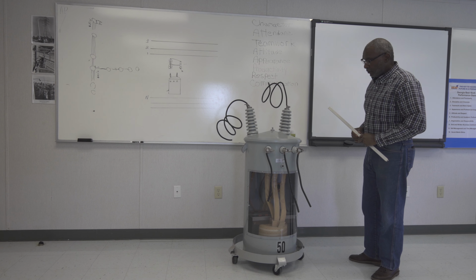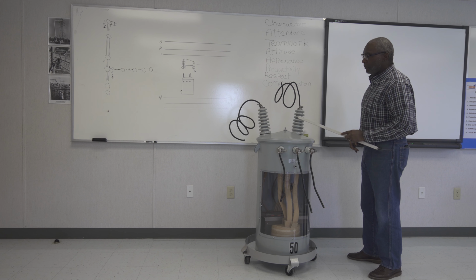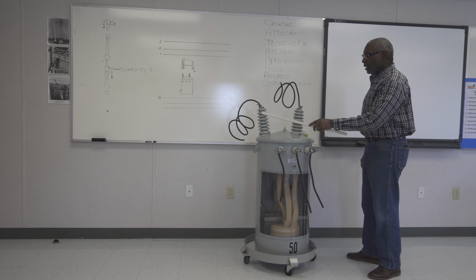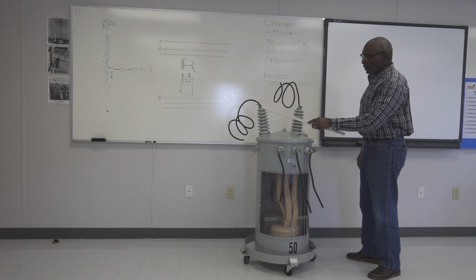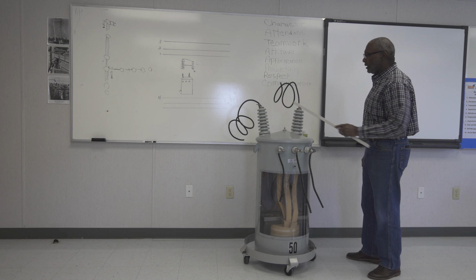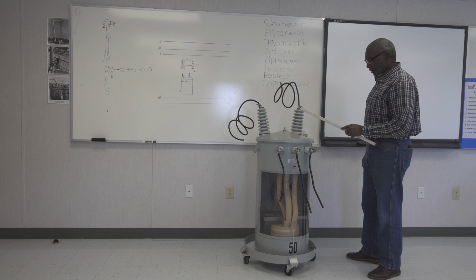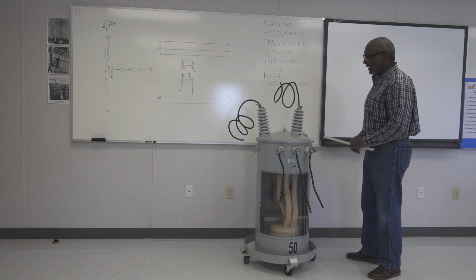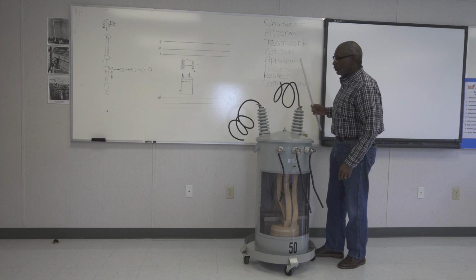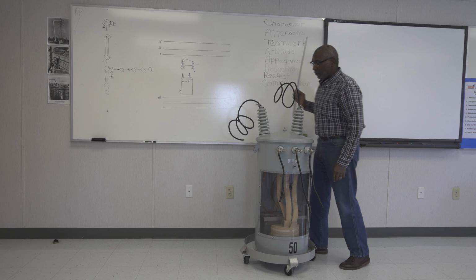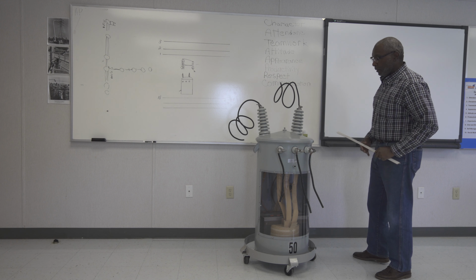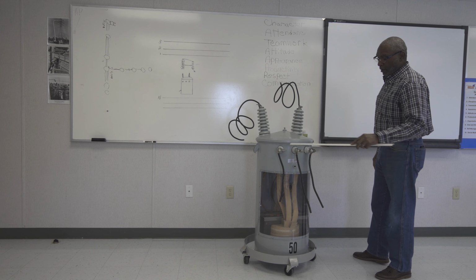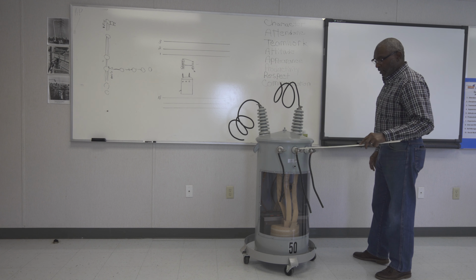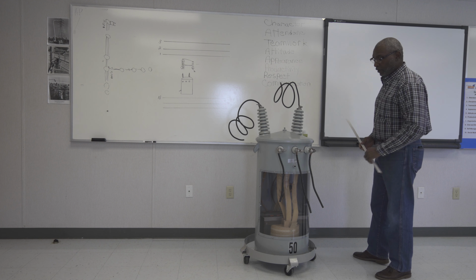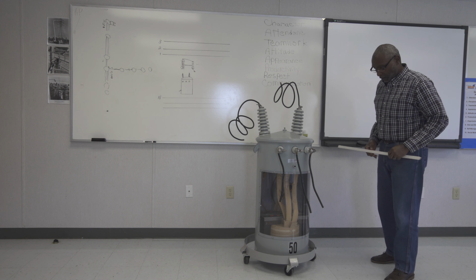So let's go back and review a little bit. High side bushing, low side bushing. This high side bushing will go to the bottom side of your switch cutout. This wire on the second high side bushing will go down to your main line neutral. Here, this wire here, and go there. On your low side, the voltage reading is 120, 120, 240 across both low side bushings.